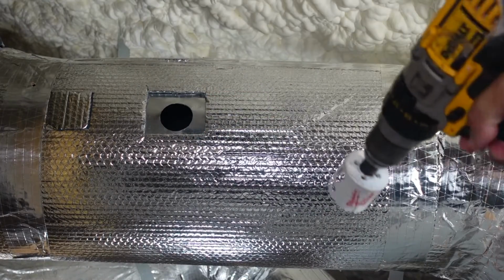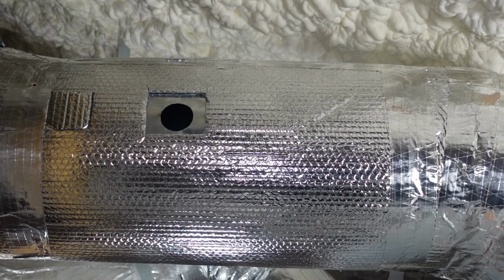Now we cut our hole in the ductwork. As mentioned, if you have an original mounting plate, cut a 1.5 inch hole for flat ductwork or a 2 inch hole for round ductwork. If you have version 2 of the mounting plate, you can use a 2 inch hole saw for any duct type. Once you're done cutting the hole, be sure to fish out any metal chunks out of the ductwork so they don't get stuck in the filter or air handler.